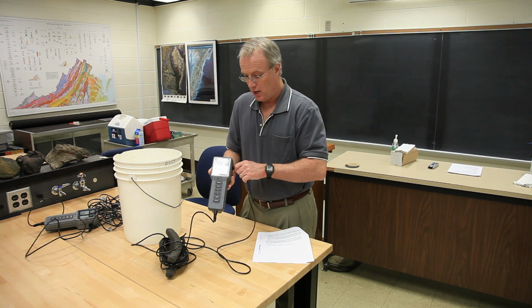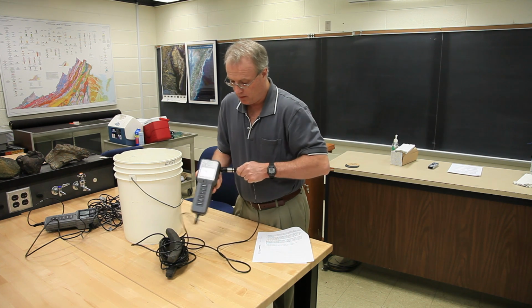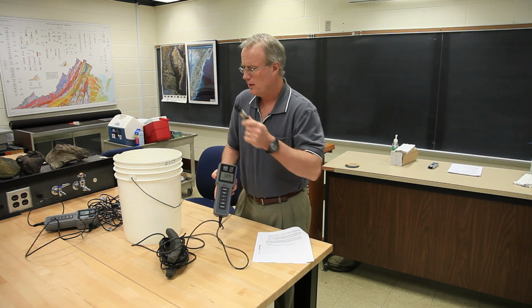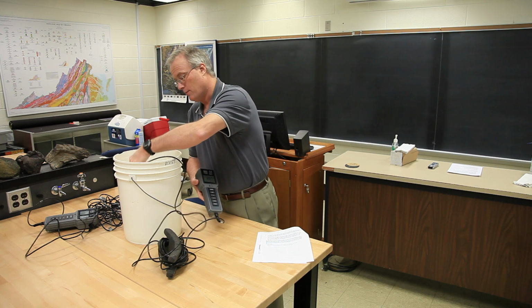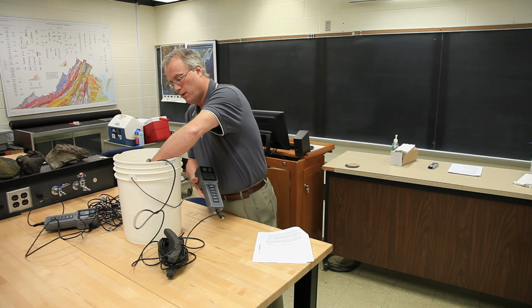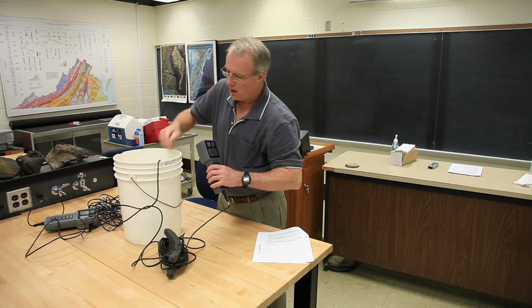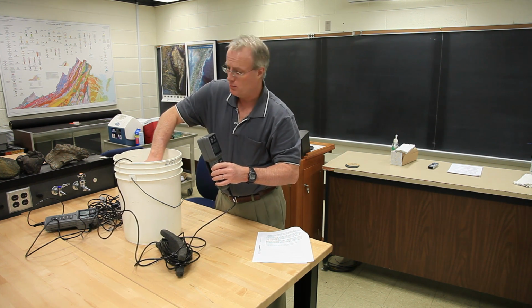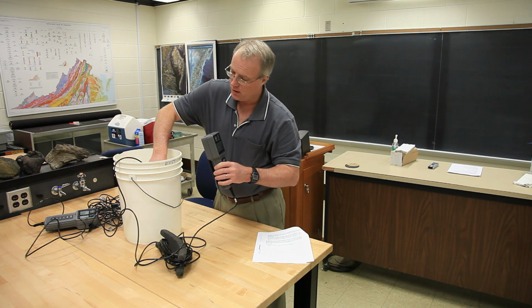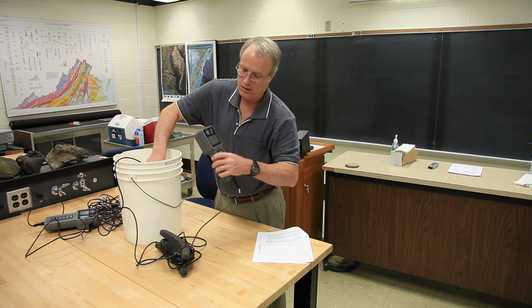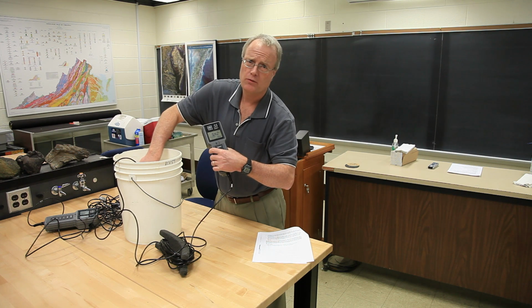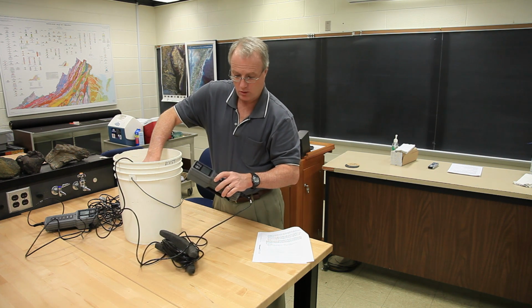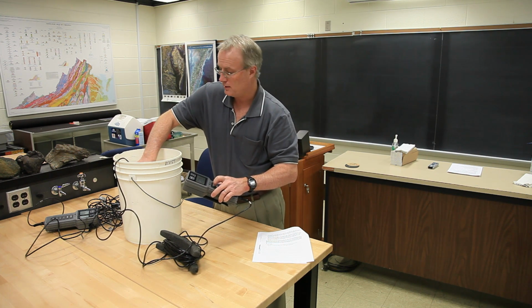To use it, you then simply take the probe out of the calibration chamber. This is my river, so pretend I'm standing in a river. I put the probe into the river. I keep it gently moving, not agitating the water quickly, not letting it just sit there unmoving, but just a very slow movement through the water, and I can take my dissolved oxygen reading right off the front of the meter. Record that on my data sheet, and you're ready to take the next measurement.